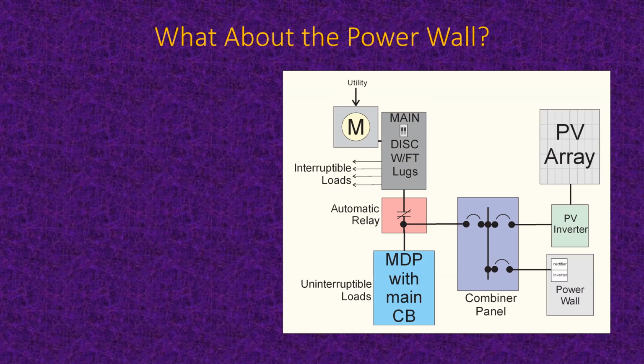So then what happens? Those switch contacts open. You've got your main distribution panel with the main circuit breaker, and those loads become uninterruptible. So we have a main disconnect with some interruptible loads on it. That would be a feed through panel up there on top. And then the bottom distribution panel may or may not have a main circuit breaker on it, but that one contains uninterruptible loads. And more than likely, it's going to have a circuit breaker, but not always.